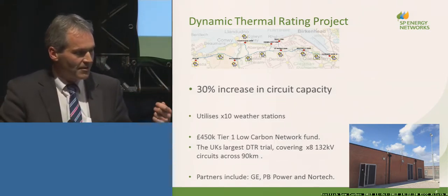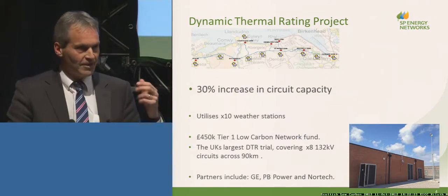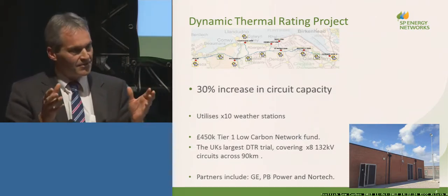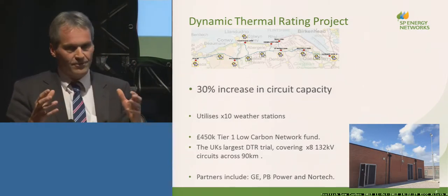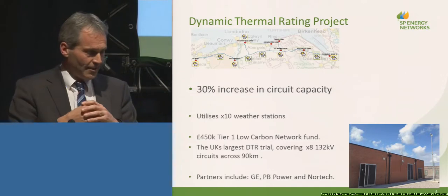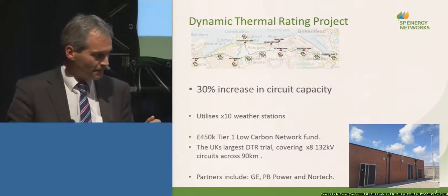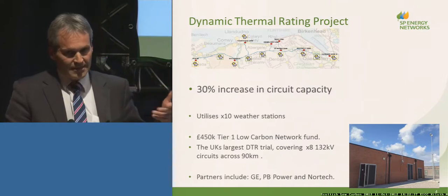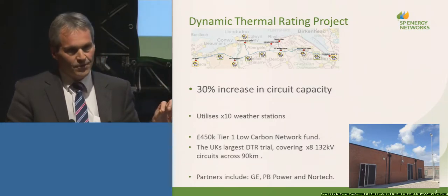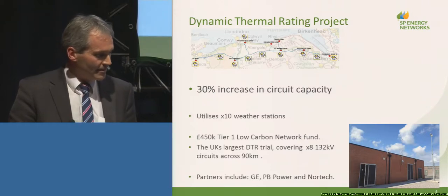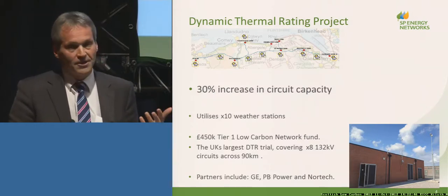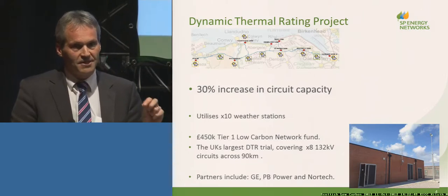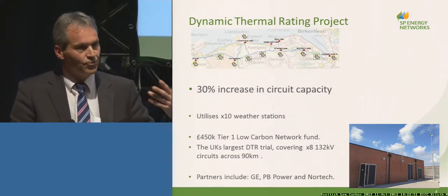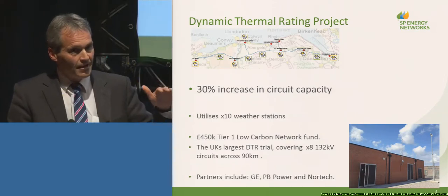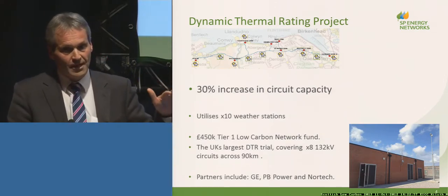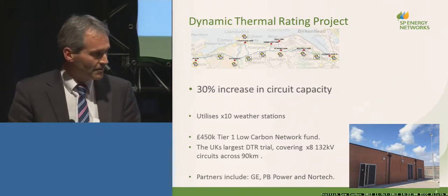So what this project is about is actually monitoring what's going on in the network. Depending on which particular model of dynamic thermal rating you go for, there's tension monitoring, temperature monitoring, all sorts of different things. You take that data, extrapolate it back, and use it to inform the current rating on your system. At the end of the day, in this particular case, that's up to a 30% increase in capacity on an existing asset, which can be significant when trying to get additional renewables into an area - you either defer significant capital investment or avoid it altogether, depending on the headroom you manage to achieve.